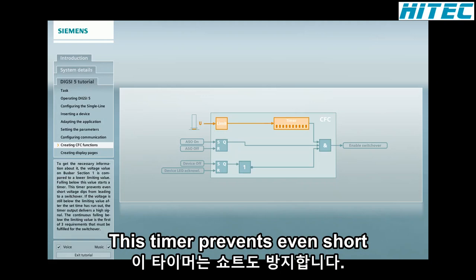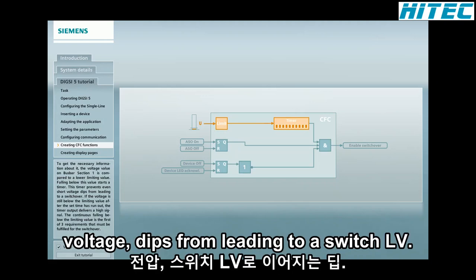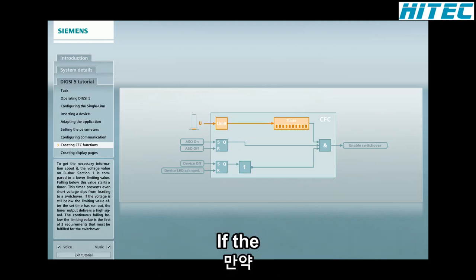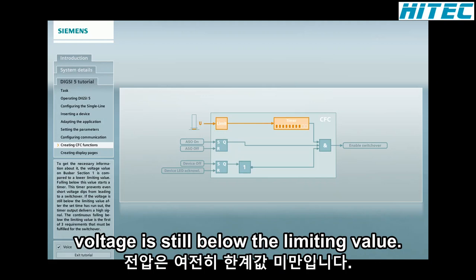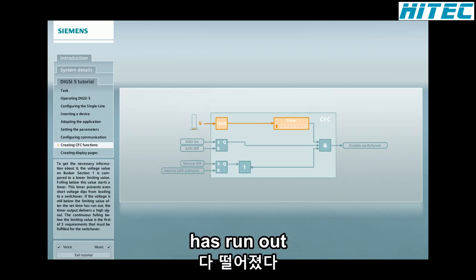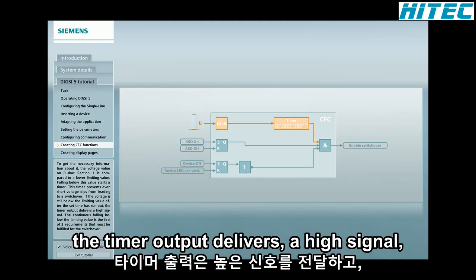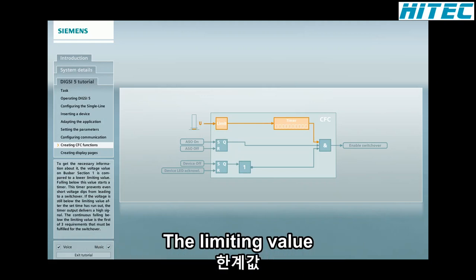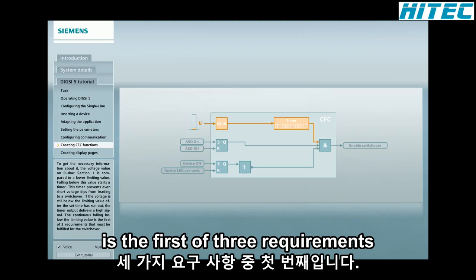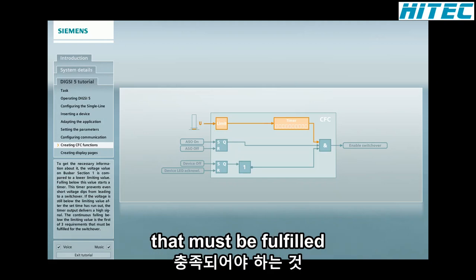This timer prevents even short voltage dips from leading to a switchover. If the voltage is still below the limiting value after the set time has run out, the timer output delivers a high signal. The continuous falling below the limiting value is the first of 3 requirements that must be fulfilled for the switchover.